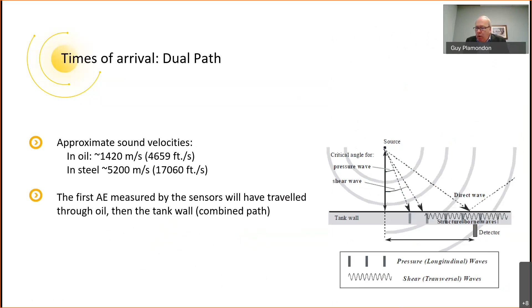Then from those clear signals, now we can calculate the time of arrival. And to do so, we have to consider that the speed of sound is not the same in the oil as it is in the steel, because the first acoustic measurement we receive will come through the tank wall itself. So it gives us what we call the combined path. And then from there, we can accurately measure the time references, either the absolute and the time difference of arrival.